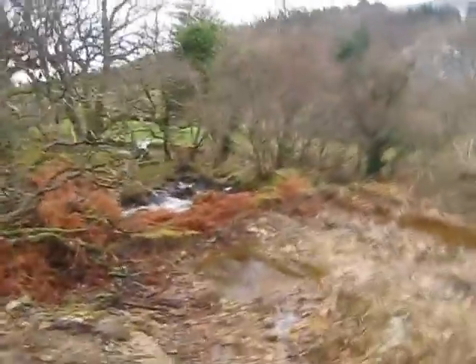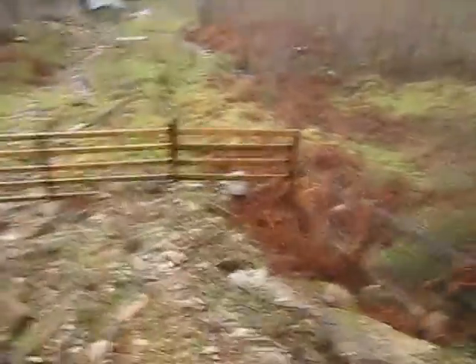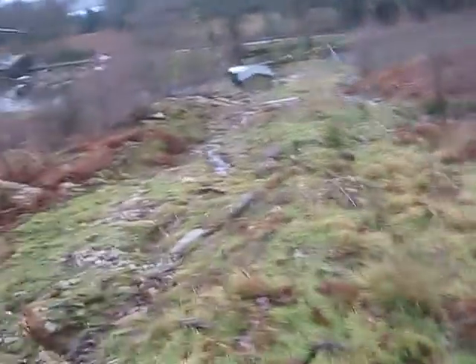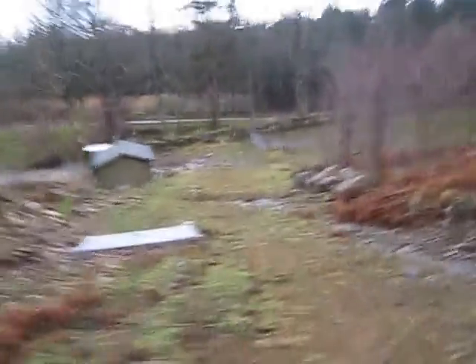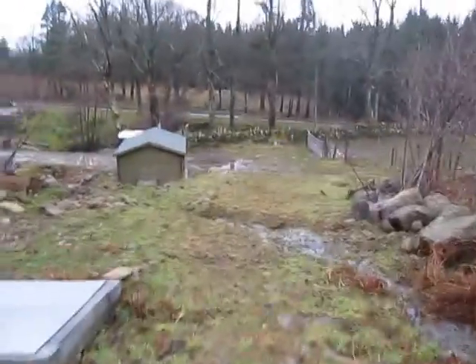You can see the river over there, raging on down as usual. Trying not to fall over as I walk down here — it's quite steep, the camera doesn't show you how steep it is. Anyway, this gives us a gross head of 40 meters, and the three pipes send water to the turbine. We get 22 kilowatts, and in the last six months it's done nearly 60,000 kilowatt hours. It hasn't really slowed down.